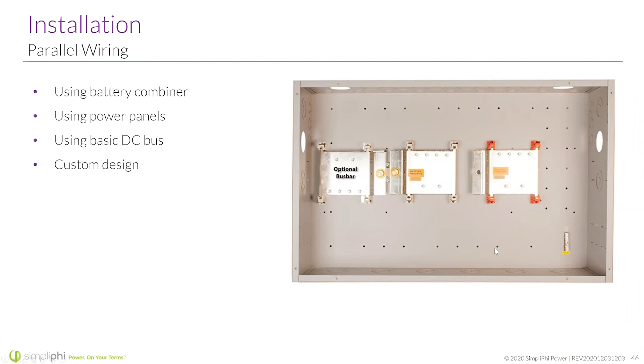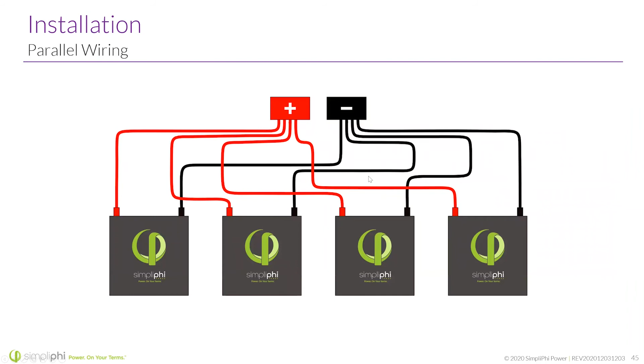I've even seen some inverters handle that connection for a couple batteries. For bigger systems, typically we're going to use battery combiner boxes like this one, or you could do terminal bus bars that go across each terminal, and then you just have a single cable going up to the connection of the inverter or the charger.